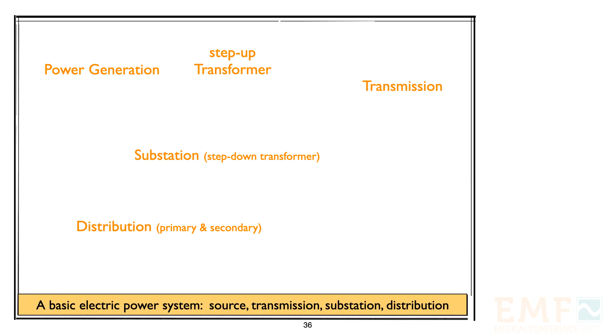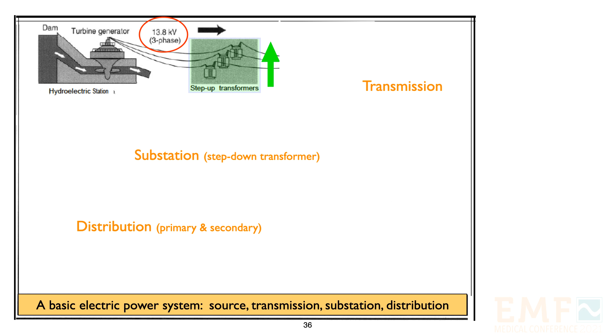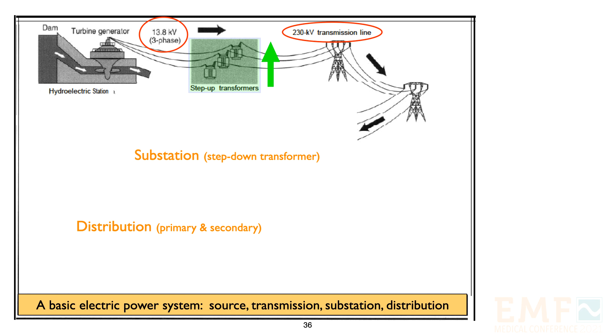We are going to take a quick tour of how electric power is distributed. We start with power generation, shown here as a 3-phase, 3-wire system at a voltage of 13.8 kilovolts. This goes through a step-up transformer whose job is to increase the voltage on the transmission line, since the higher the voltage, the less power lost with long-distance transmission. Here we have a 230 kilovolt transmission line.